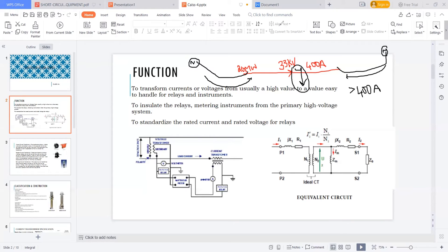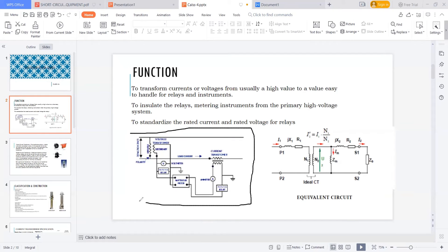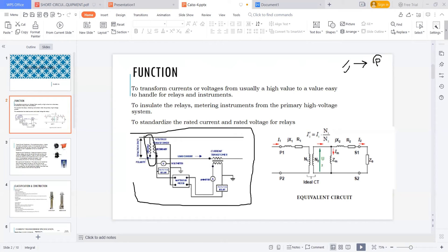Here you can see a circuit drawing where this is the 33 kV line. Voltage transformers are always connected in parallel to the line because voltage is calculated phase to ground. The current transformer is connected in series to the line to calculate the line currents. Both the voltage transformer and current transformer are connected to watt meters, relays, ammeters, voltmeters, or whatever application you have.